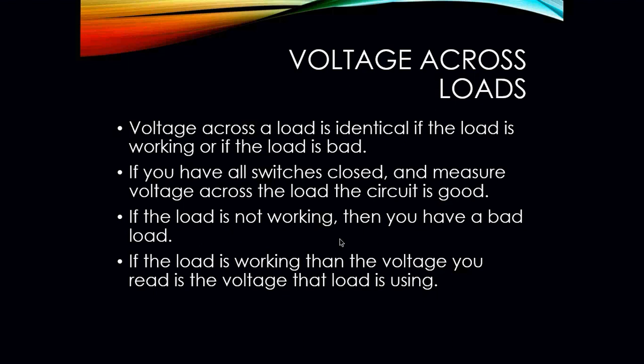Voltage across a load is identical whether the load is working or not working, or if it's bad. If you have a switch closed and measure voltage across the load, the circuit is good. If the load is not working, then you have a load that is bad. At that point, we would have to take troubleshooting a little bit further and use resistance to figure out exactly where the problem is. Is it a broken wire? Is it the load itself that is no good? If the load is working, then the voltage you read is the voltage that the load is actually using.